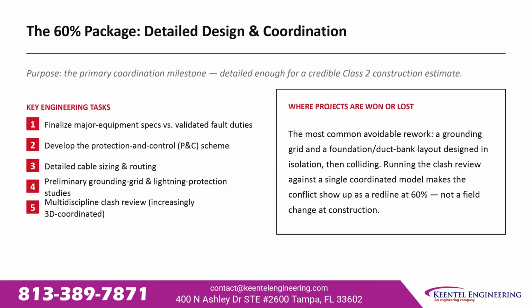The 60% package is the primary coordination milestone, detailed enough for a credible Class 2 construction cost estimate. The key tasks at 60% are finalizing major equipment specifications against validated fault duties, developing the protection and control scheme, detailed cable sizing and routing, preliminary grounding grid and lightning protection studies, and a multidiscipline clash review, increasingly conducted against a coordinated 3D model. This is where projects are won or lost.